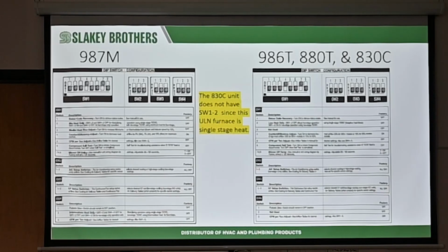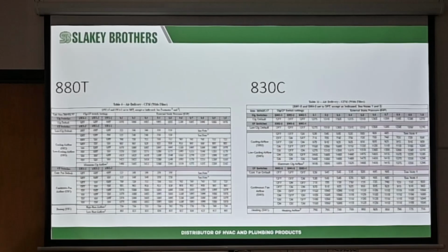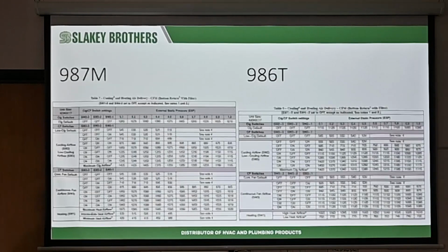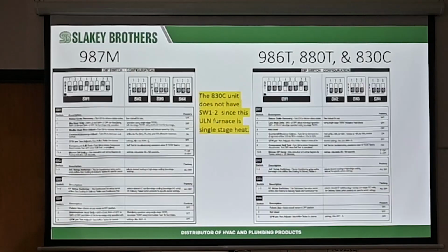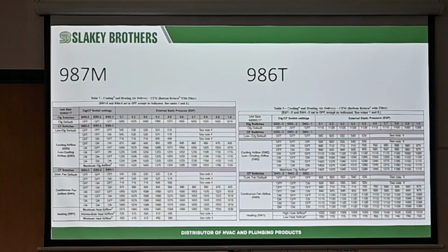So first thing is, of course, I think we're talking about just make sure your airflows are all set up properly. Okay, so non-evolution, again, make sure your airflows are set up for each particular furnace, whatever you may have. Make sure you have the right set points per each particular unit. So for instance, if you're doing a standard thermostat, you want to go to the particular furnace that you have. So like this one here is a 42,000, 42, 60, 17 inch. So meaning that that's generally 3.5 tons, 60,000 BTUs of gas heat, 17-inch wide furnace.